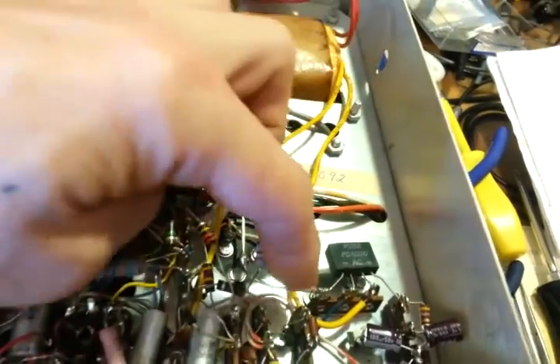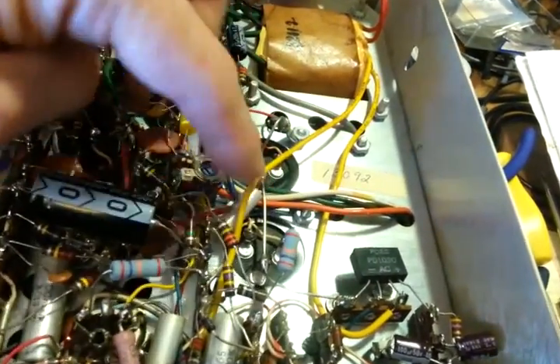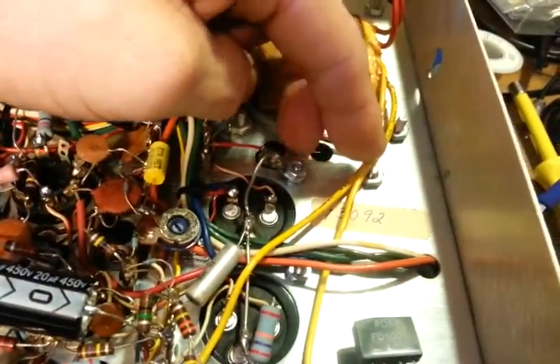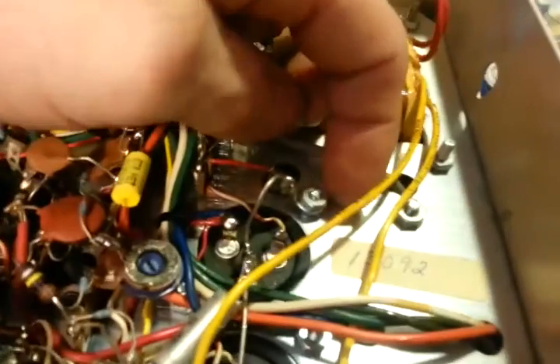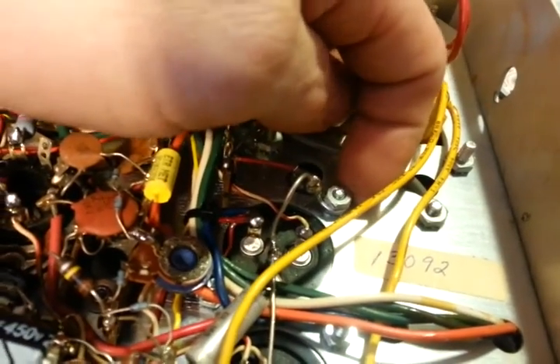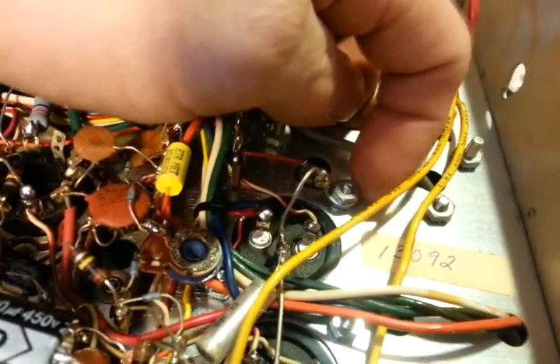And I'll find a factory one, because they use the rivet. Now there's a star washer underneath of these lugs, so I'll always tie to one of those usually on one side, and then I'll add one on the other side, and I usually go off the nut that I installed, and I use star washers also. So actually that's double nutted. There's a screw that comes up from the clamp, a star washer, a nut, then I install an eyelet terminal.